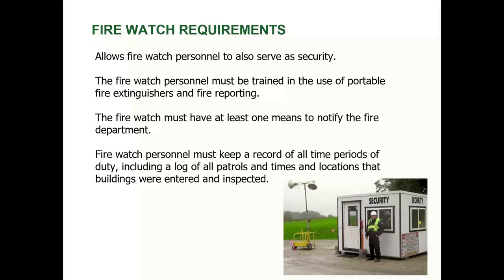And I told you a little bit about the Rockville fire where they had a guard service, but the guard service didn't patrol. So that heater ran from Friday when those folks left up in that upper floor all weekend long and caught the debris on fire, and it burned up into the roof. And the roof had a dry sprinkler system. But guess what? The dry sprinkler system wasn't turned on. It was working, it had been approved, but it was a very cold March.